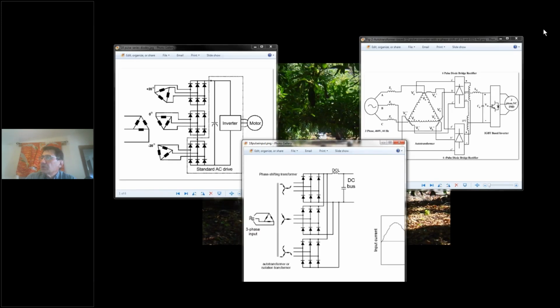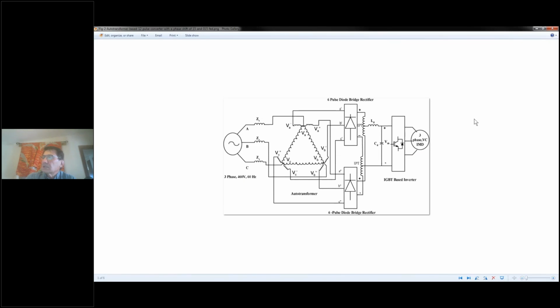There's a technology out there that was used primarily for cost reasons. I don't see a lot of technical advantages, but this is using an auto transformer, which, as you can see, does not have any galvanic isolation. This is completely incompatible with the galvanically isolated primaries and secondaries of a standard 18 pulse transformer, or 12 pulse transformer. This happens to be a 12 pulse setup. You can do these auto transformer situations with an 18 pulse.